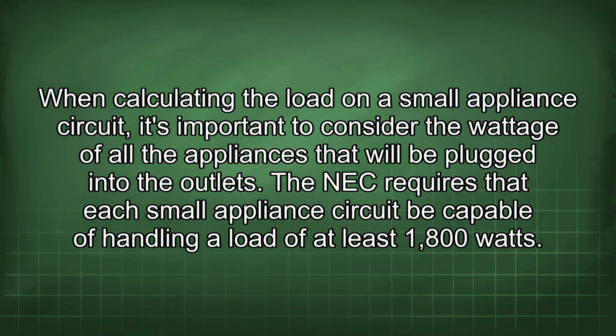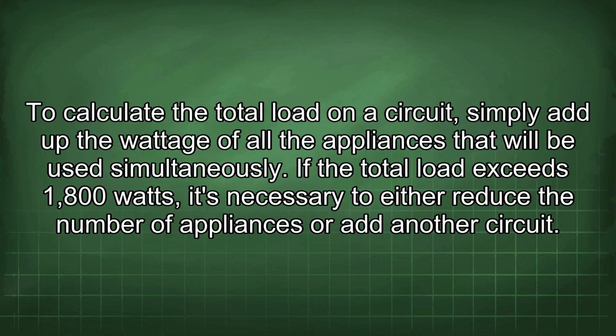When calculating the load on a small appliance circuit, it's important to consider the wattage of all the appliances that will be plugged into the outlets. The NEC requires that each small appliance circuit be capable of handling a load of at least 1800 watts. To calculate the total load on a circuit, simply add up the wattage of all the appliances that will be used simultaneously. If the total load exceeds 1800 watts, it's necessary to either reduce the number of appliances or add another circuit.